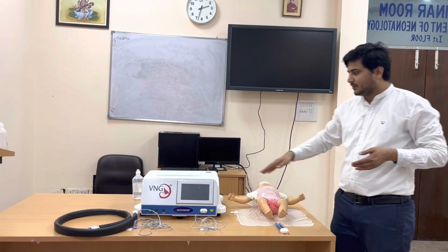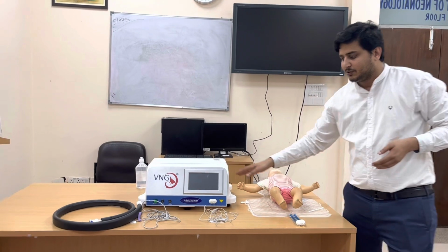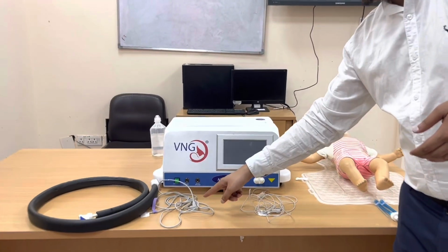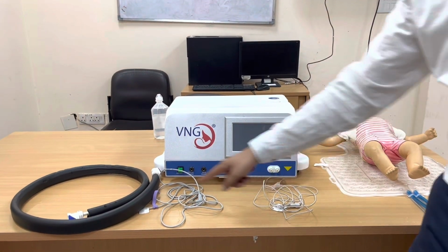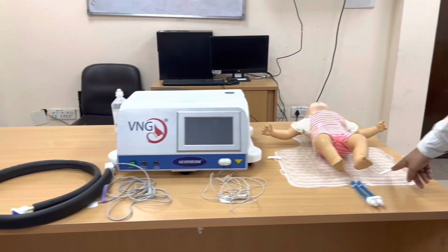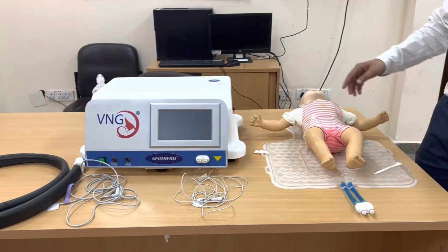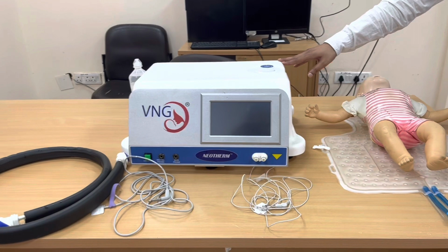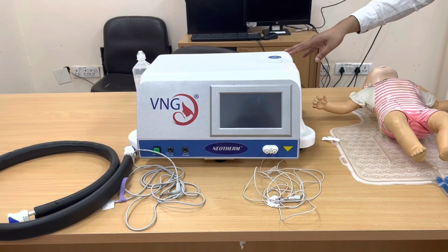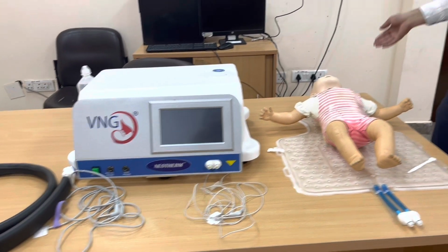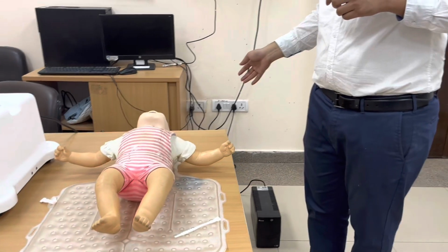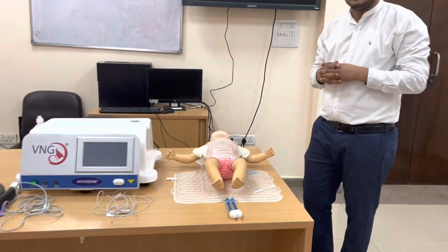The whole coolant system consists of the main device, disposable temperature probes, one skin and the other rectal, a hose system and a cooling mattress. Since this device has no inbuilt battery backup, it is advisable to connect this device to a UPS device to prevent interruption of therapeutic hypothermia in cases of power failure.